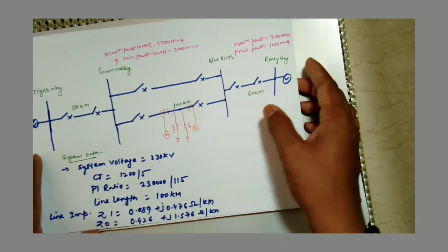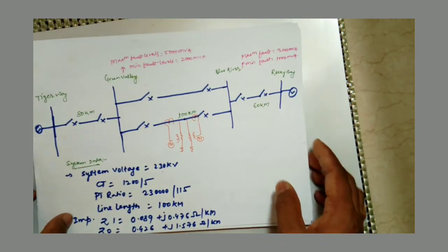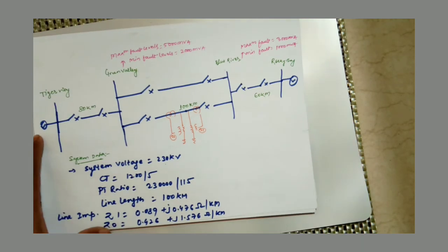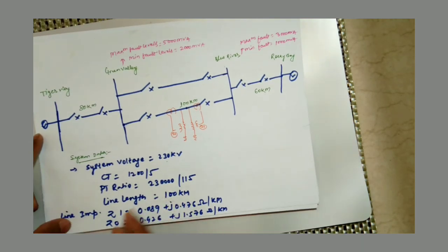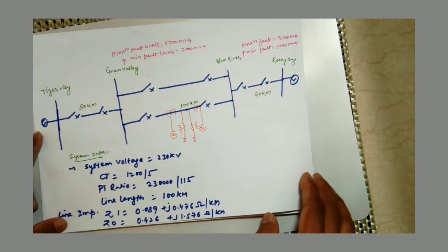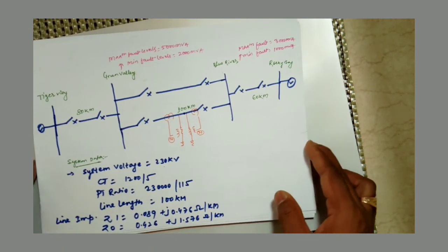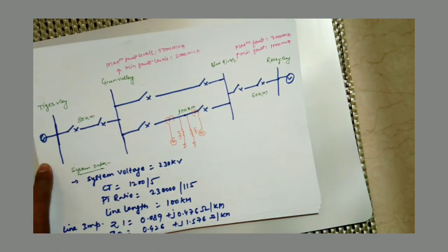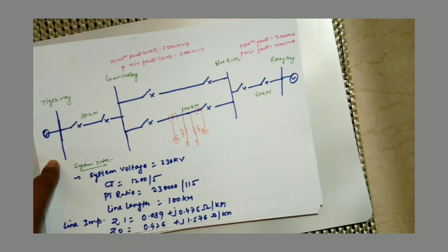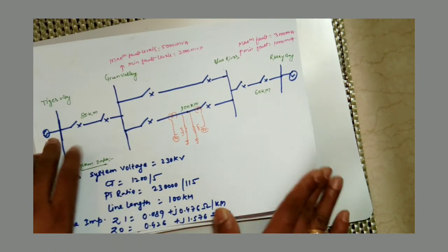So just go through the relay manuals, or you can check the relay parameters. You will have all these things to put in, like the compensation factor; you have to enter the values of Z1, Z2, Z3, Z4 in the relay. Apart from that, you also have to put in the phase resistive reach value for each zone.